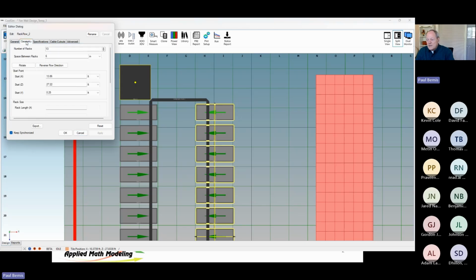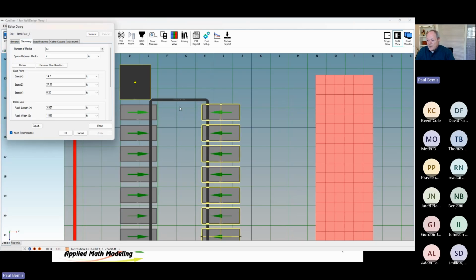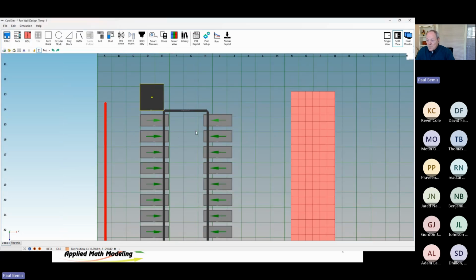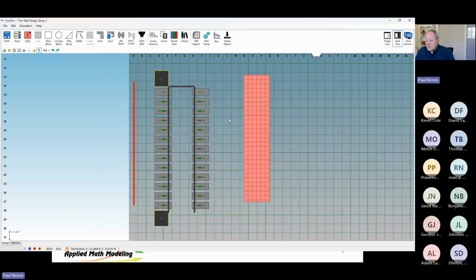I'm going to move this rack over a little bit. It's starting at 13.86. I'm going to start it at least at 14. Let it move over a bit. So that's a little bit better. Might go a little bit more, 14.5. Just move it over so that you have enough room in that hot aisle. Here I'm about 5 feet in that hot aisle. That's really what I want. You want these to be as wide as you can possibly get them. It's expensive to do that because, of course, you're spending money on infrastructure. White space is important. But nonetheless, you want these things to be wide so that you do not have pressure problems.